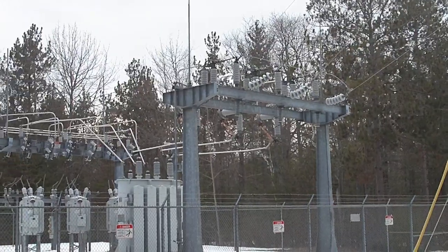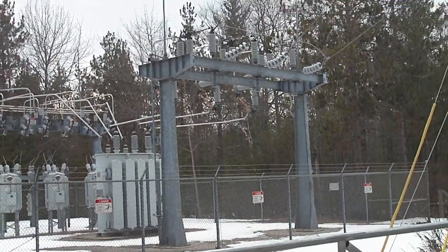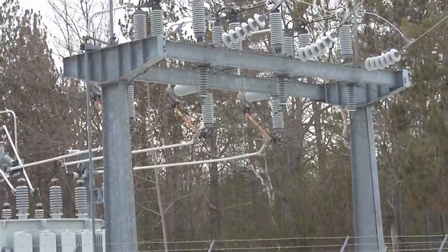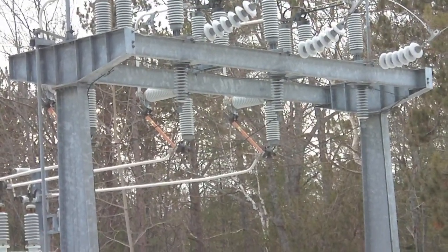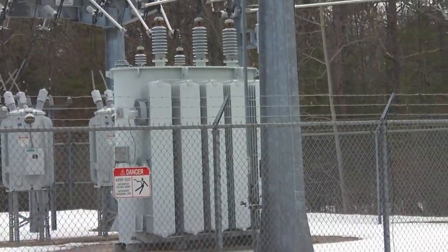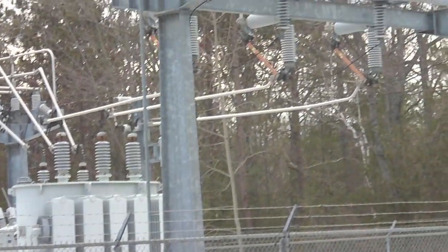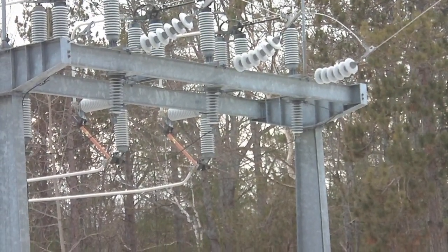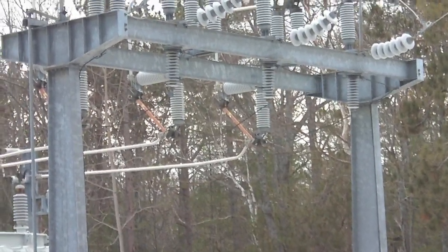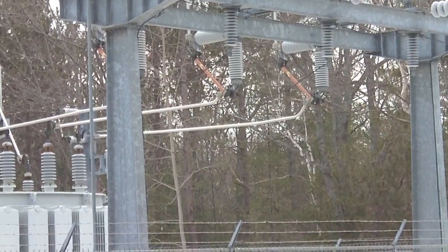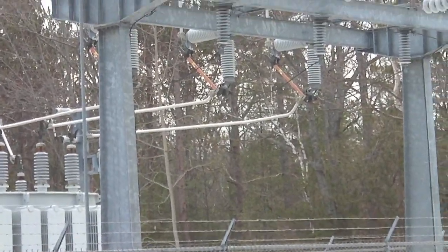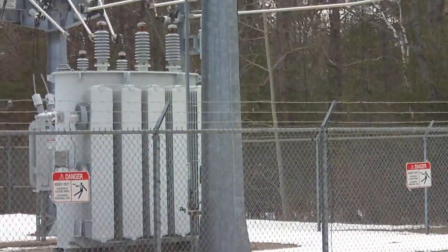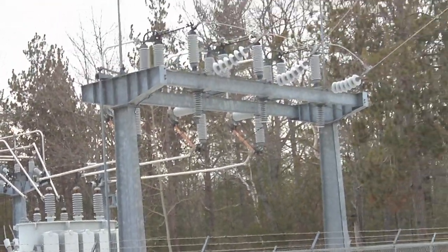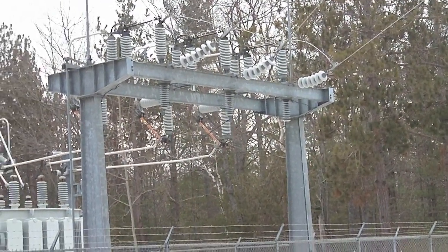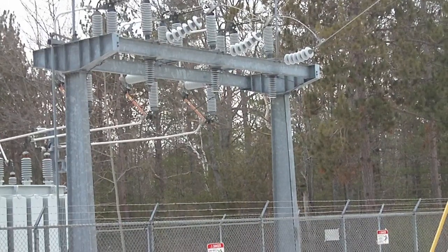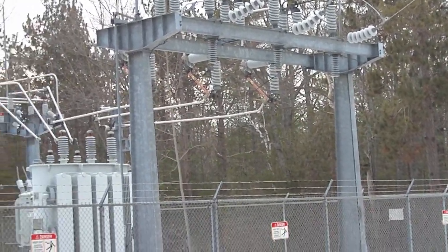Moving on to the left of that, on the back side, you can see the orange high side fuses. That's really the only protection for this bad boy, which is the power transformer. Most modern substations today have something other than just fuses. They'll have circuit breakers and things like that, with CTs and PTs and everything to protect this guy. But with this older substation, all we have is those high side fuses, very similar to the cutout that you're used to working with already.